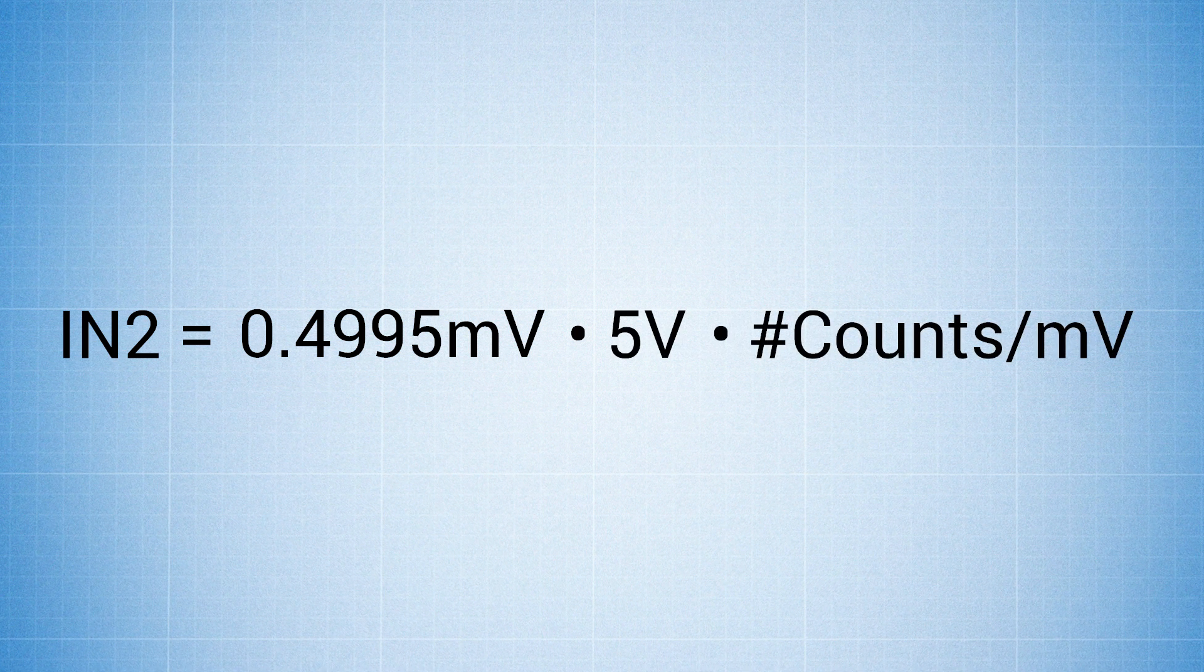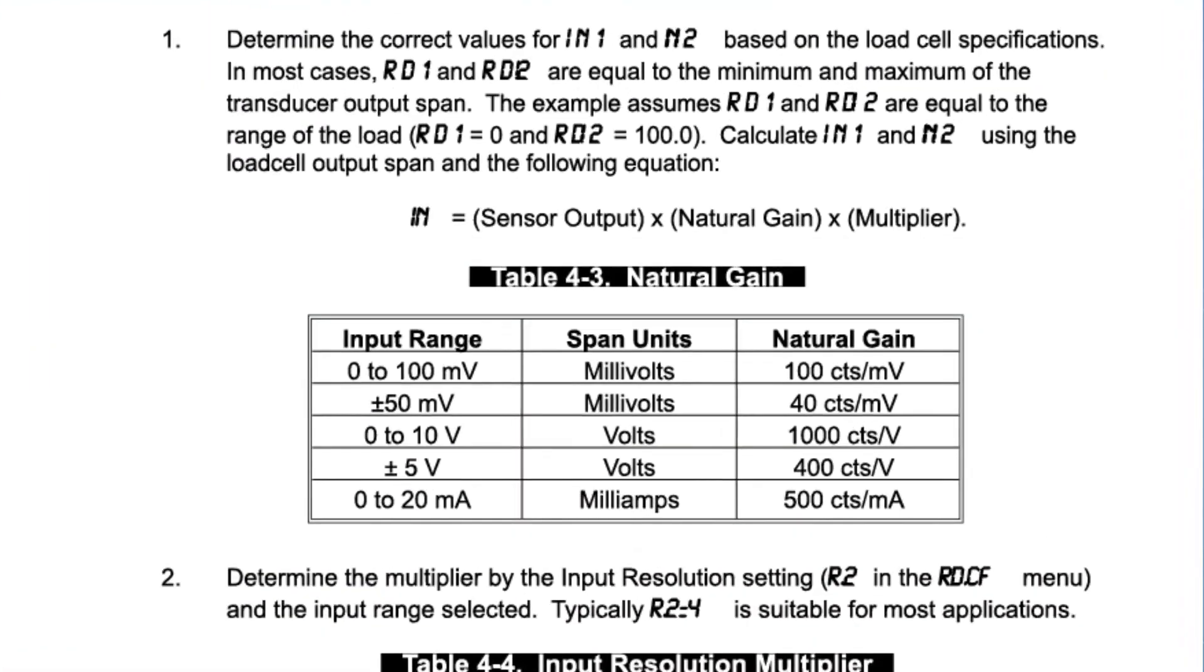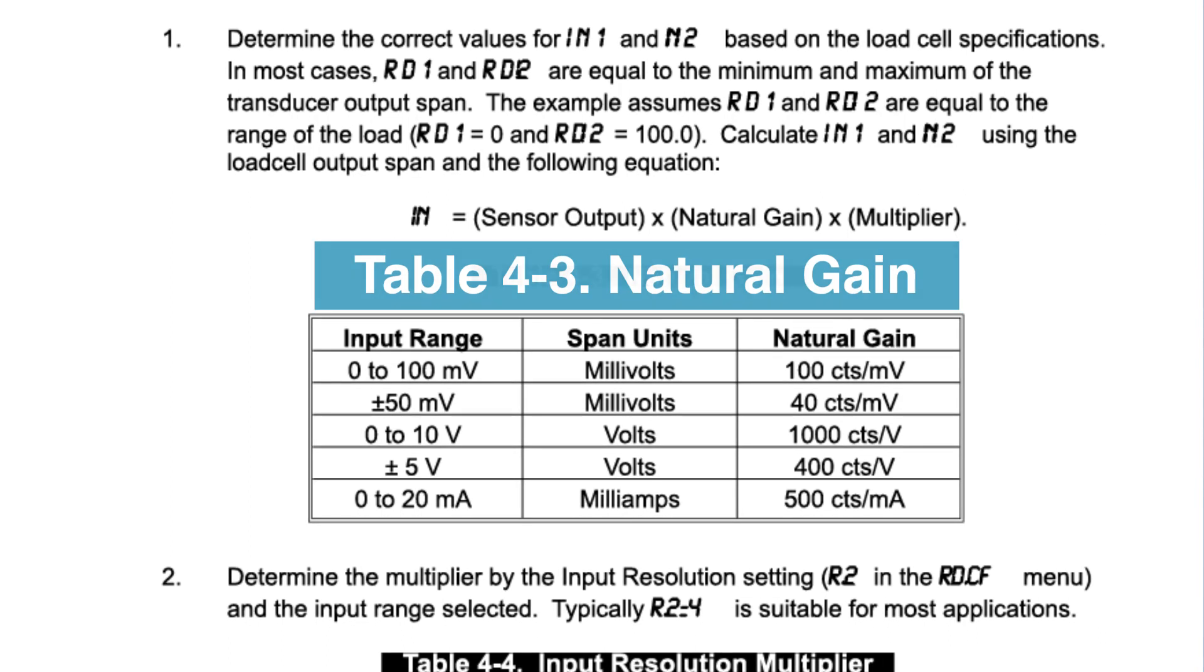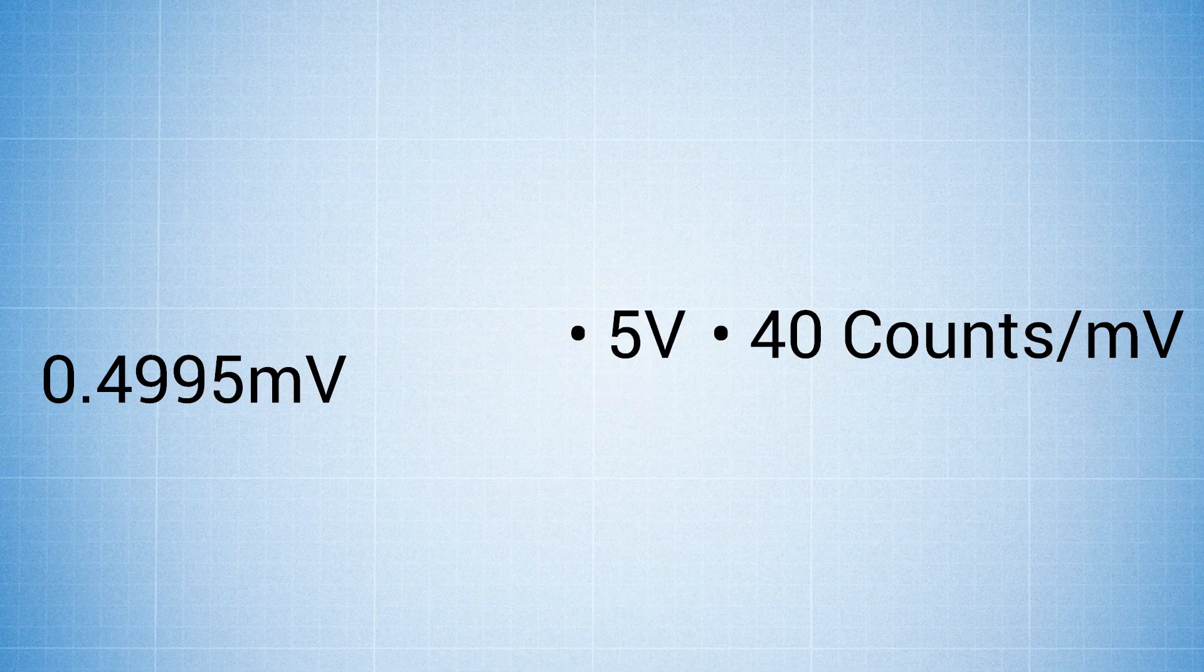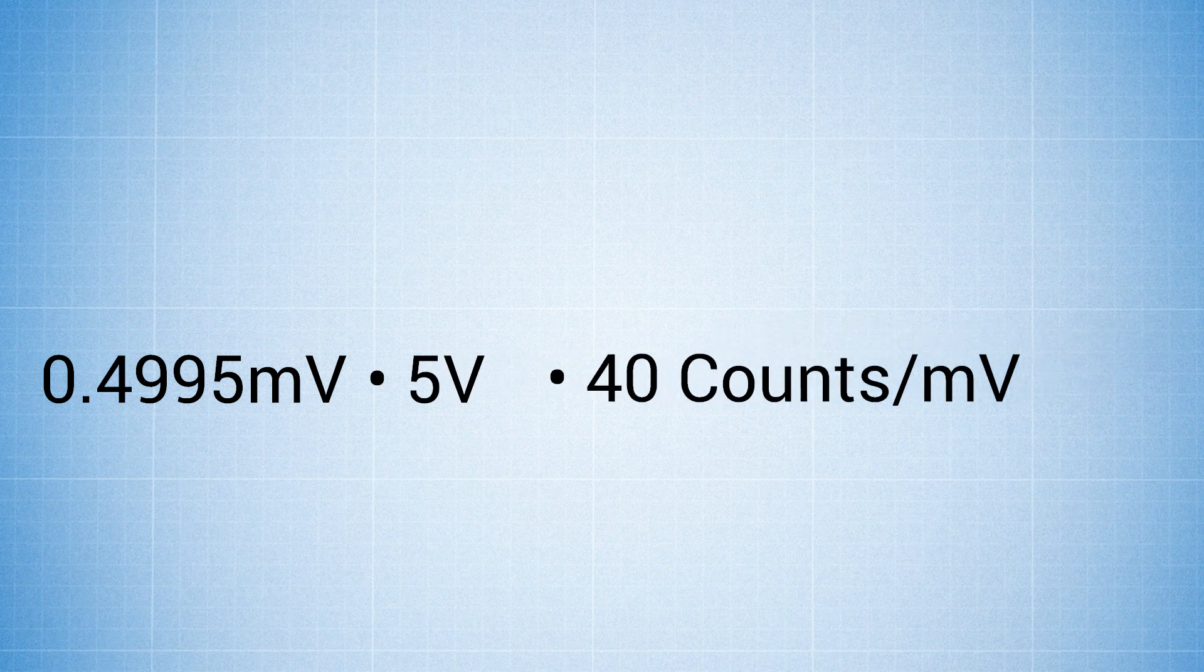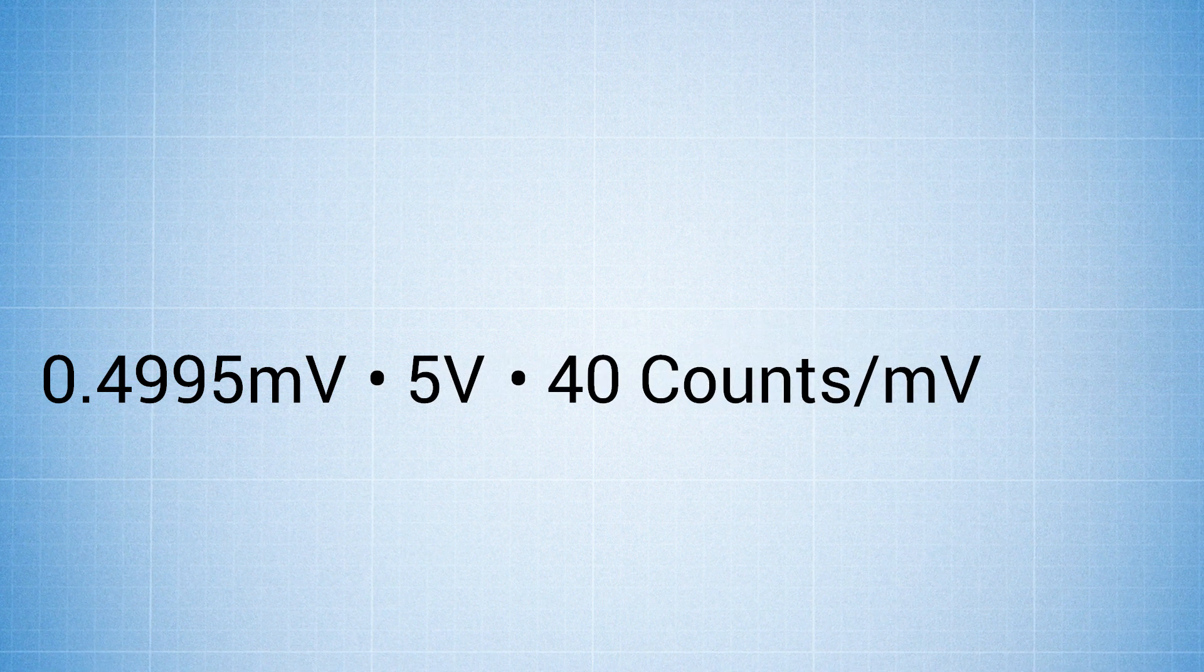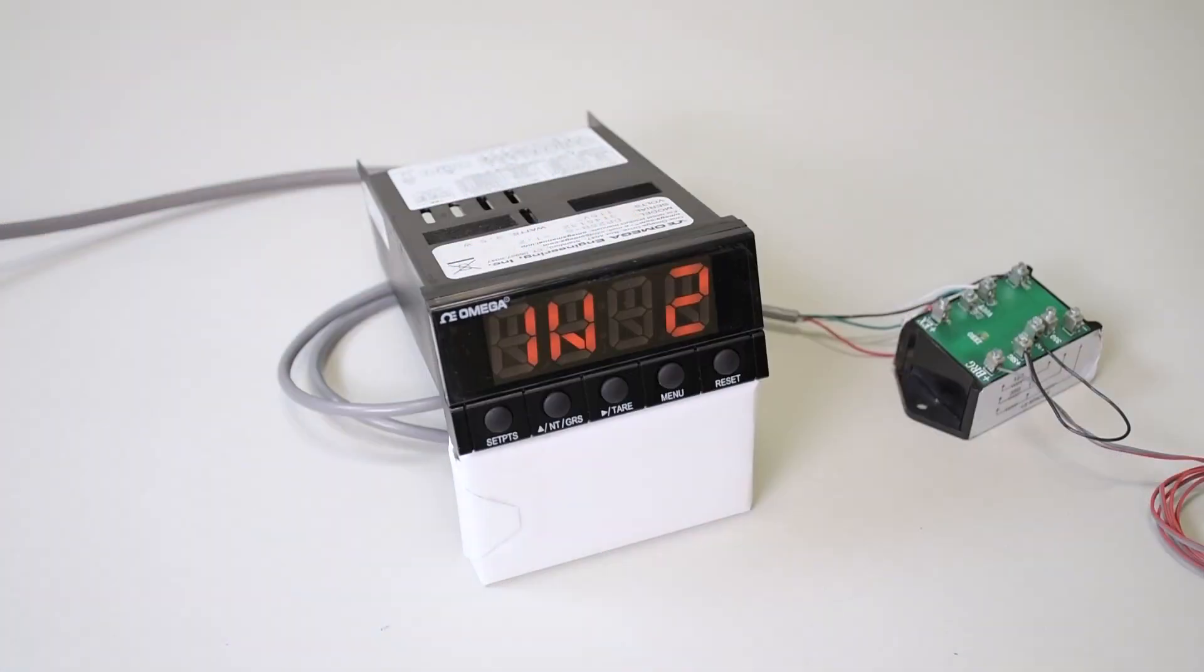Multiply that with the number of counts per millivolt. If you want to know the number of counts per millivolt corresponding to the input range, see page 26 of the DP25B-S manual. Look under natural gain. For plus or minus 50 millivolts, natural gain is 40 counts per millivolt. 0.4995 millivolts per volt multiplied by 5 volts multiplied by 40 counts per millivolt gives you 99.9. That's exactly what we're going to put in IN2.